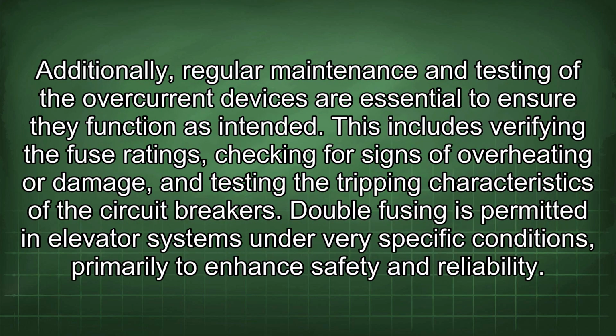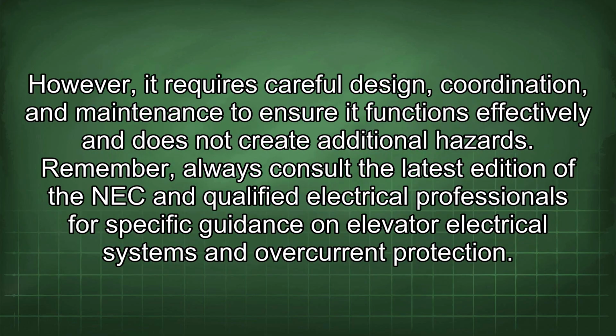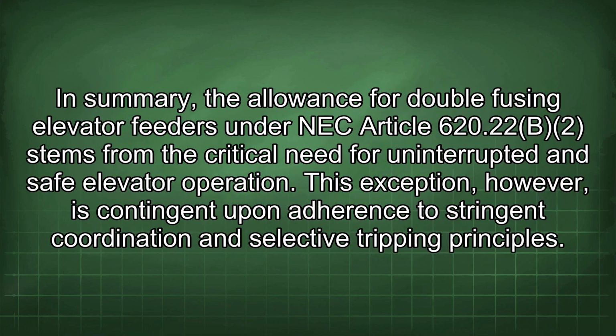Additionally, regular maintenance and testing of the overcurrent devices are essential to ensure they function as intended. This includes verifying the fuse ratings, checking for signs of overheating or damage, and testing the tripping characteristics of the circuit breakers. Double fusing is permitted in elevator systems under very specific conditions, primarily to enhance safety and reliability. However, it requires careful design coordination and maintenance to ensure it functions effectively and does not create additional hazards. Remember, always consult the latest edition of the NEC and qualified electrical professionals for specific guidance on elevator electrical systems and overcurrent protection.